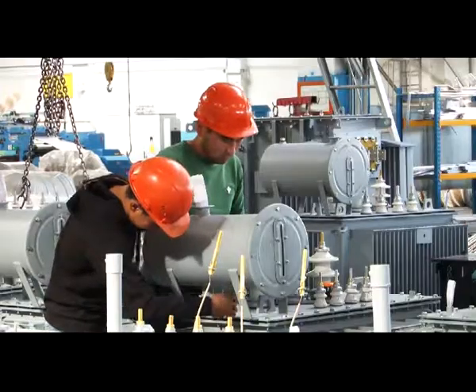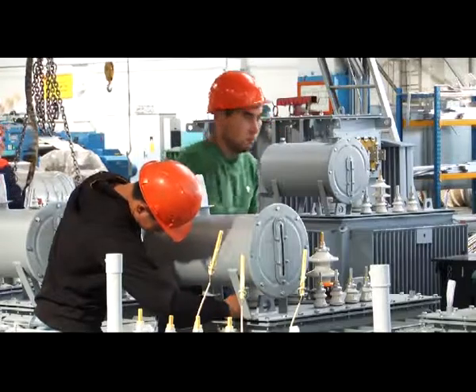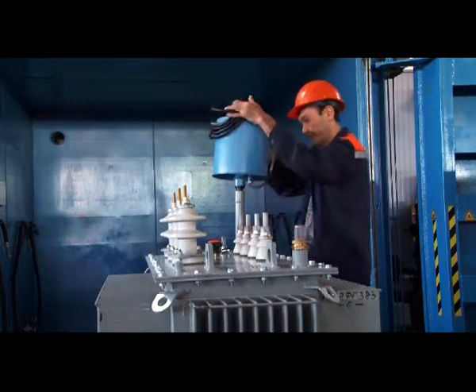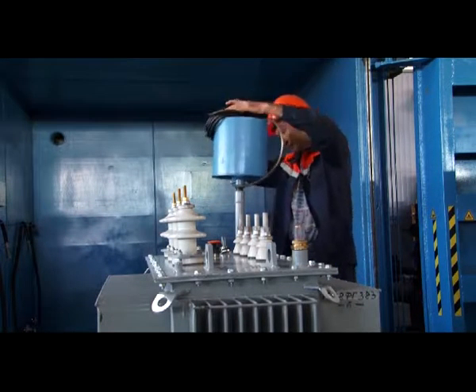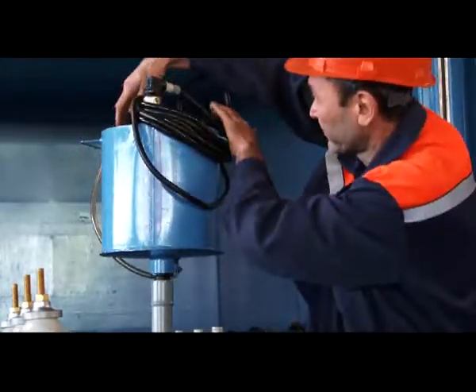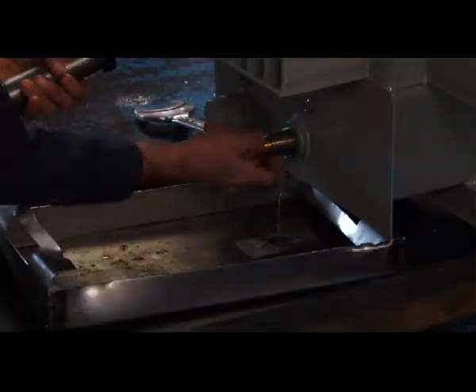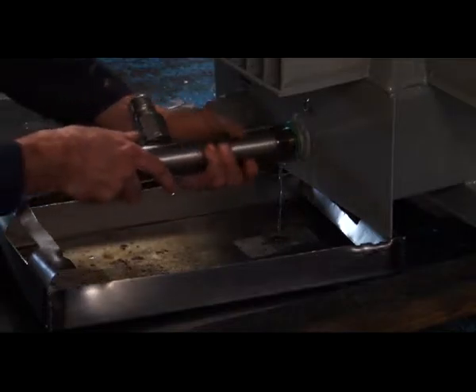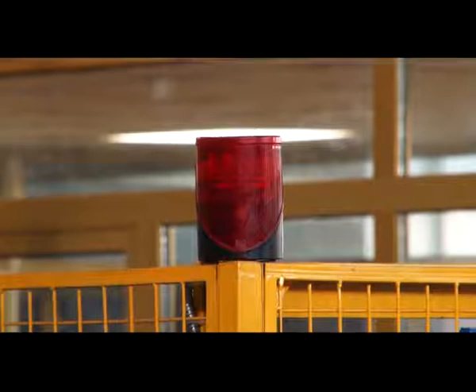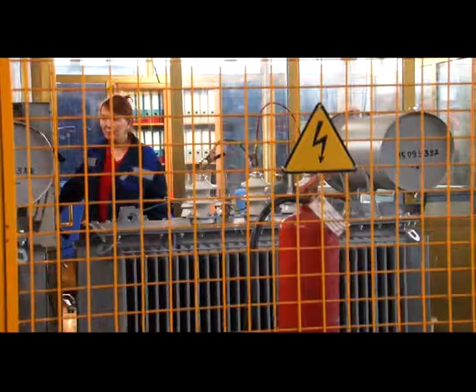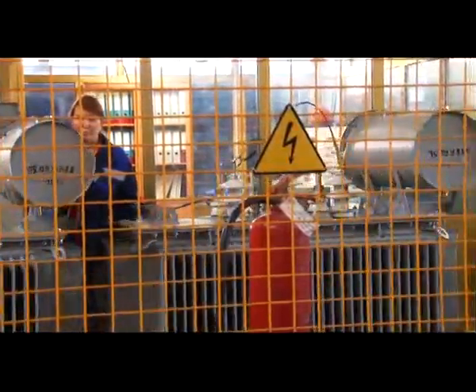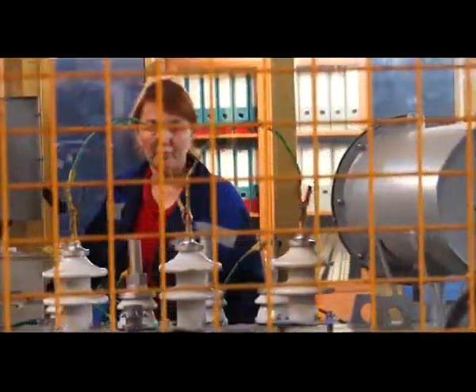Now the tank needs to be filled with transformer oil. This is done in a vacuum in order to remove all air from the inside, so that only oil remains inside the transformer. After it is filled with oil, the transformer is considered almost finished. But before it is packaged, it is tested here at the plant by connecting it to an electric station and checking the performance indicators under various operational regimes.